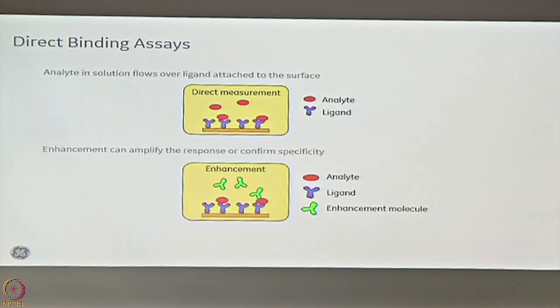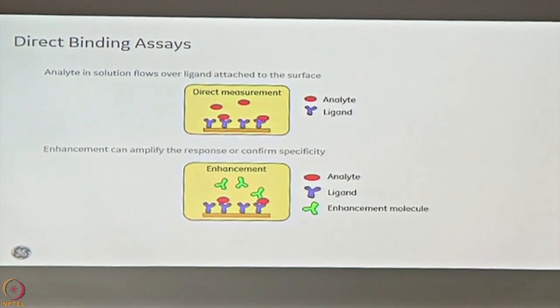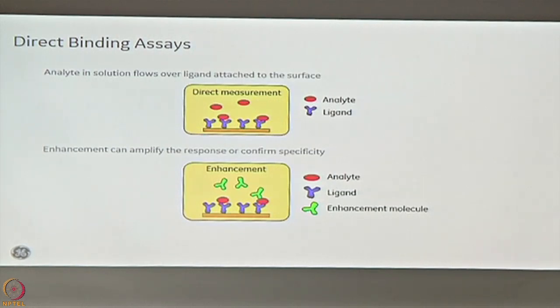The first assay format is the direct binding assay format, which is very simple. Your interactant is immobilized on the surface. In Biacore, whatever goes on the surface is called the ligand, and whatever is flown on the flow cell is called the analyte. In the direct binding format, your ligand is covalently linked to the surface and your analyte is moving on top.